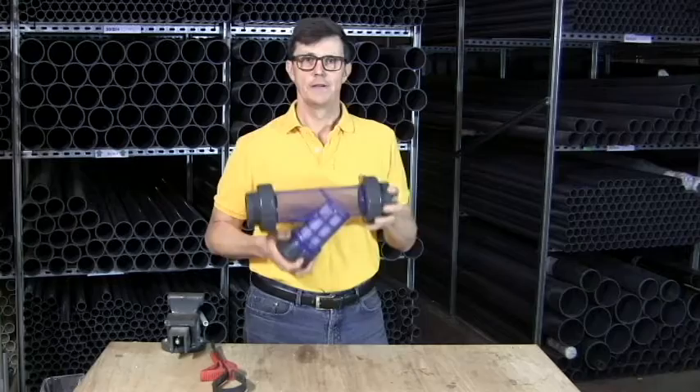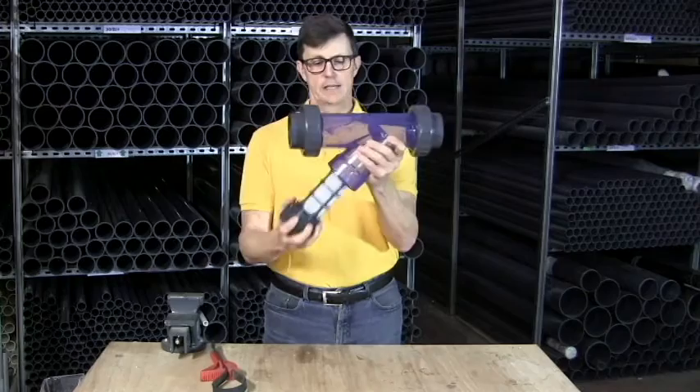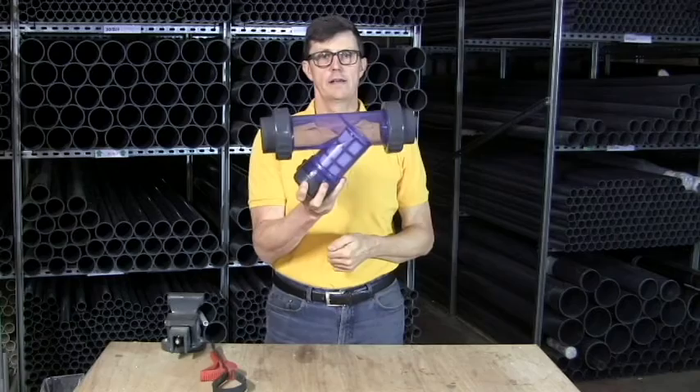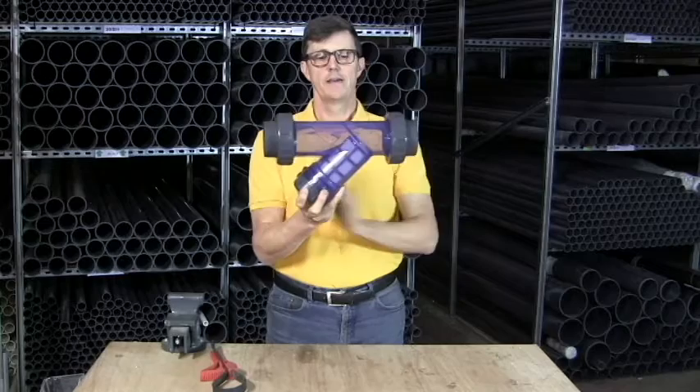A Y strainer mounts in the line with the Y pointing downwards — that makes it easy to get the strainer out, clean it, and then put it back in again. The flow rate is coming from this way and coming out of the strainer the other way. The flow comes in, goes inside the strainer, flows through the strainer, and then comes out nice and clean on the other side.